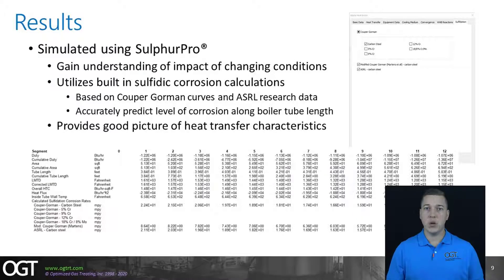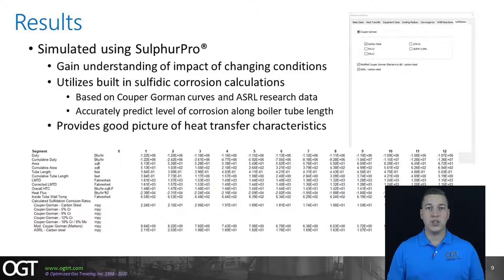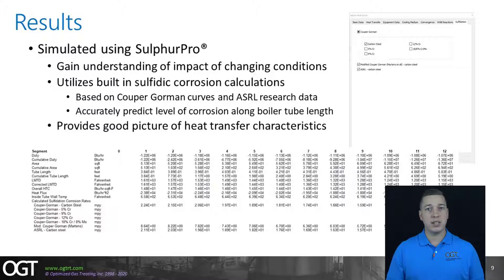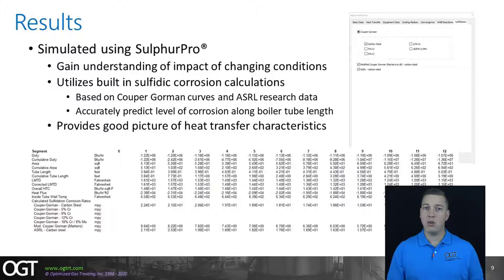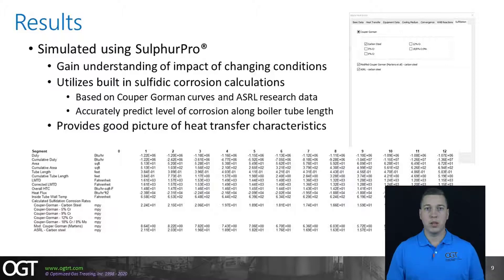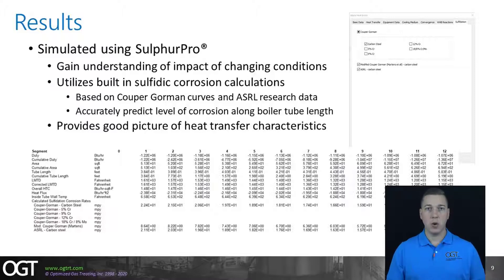A model of this plant was set up using OGT's kinetic and heat transfer rate-based sulfur simulator, SulphurPro, to gain a good understanding of how adding oxygen enrichment would affect the general operating parameters of the plant. This simulator has a sulfidic corrosion prediction model built right into the calculations, so these values are calculated as part of the model's output. The available corrosion models are the original Couper Gorman curves, the ASRL research data, and the modified Couper Gorman curves from Martens et al. The model used for this study was the original Couper Gorman curves, as these had been validated by ASRL and were felt to give the best representation of what was going on within the tubes.